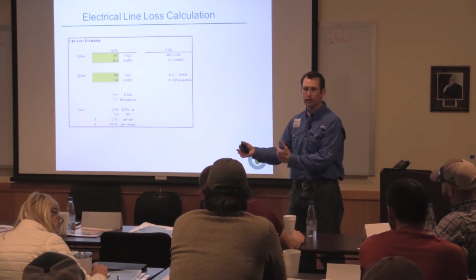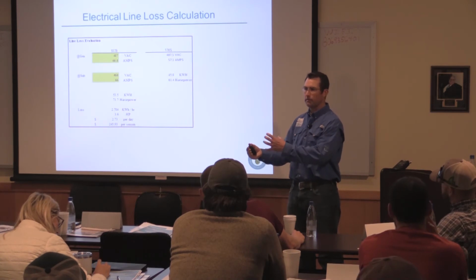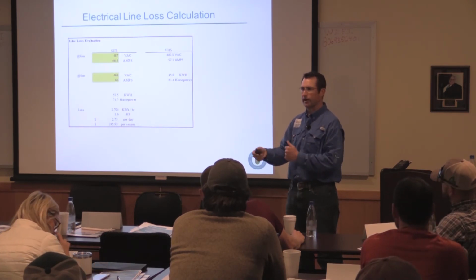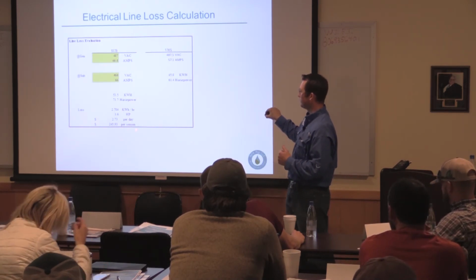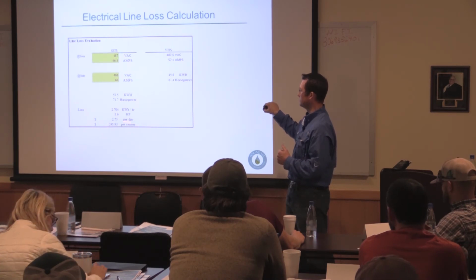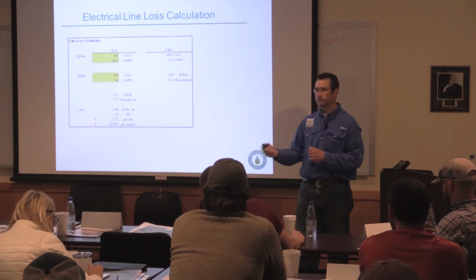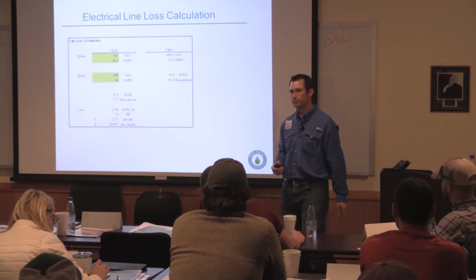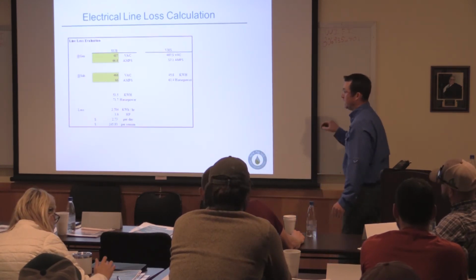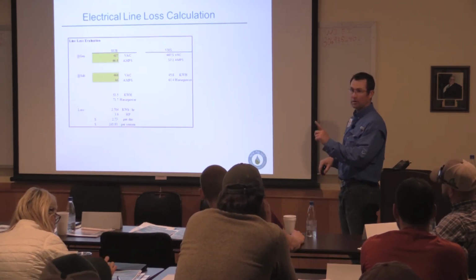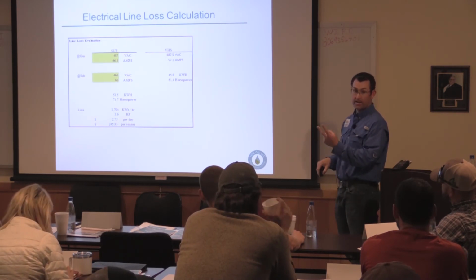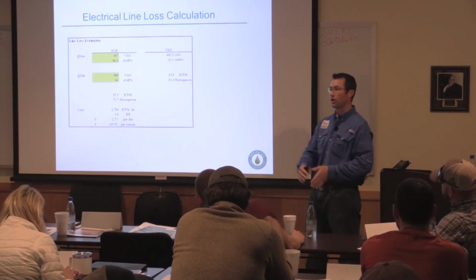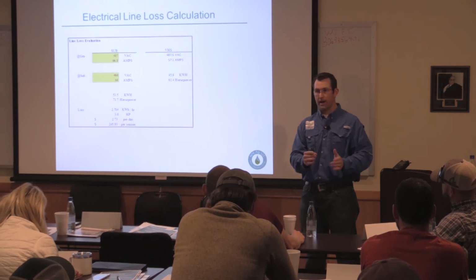which to me is a number that says that this line was sized properly. Okay, if you went one size up, I don't think the economics of sizing up one size and get this down to say $5 per season, it would take a lot of years to accommodate that $200 savings, you know, with what your additional input cost is. But you want to run through these numbers. If you get this wrong, you've really only got one time to do it, or you're buying it again. And you're going to be better safe than sorry, size up rather than down.